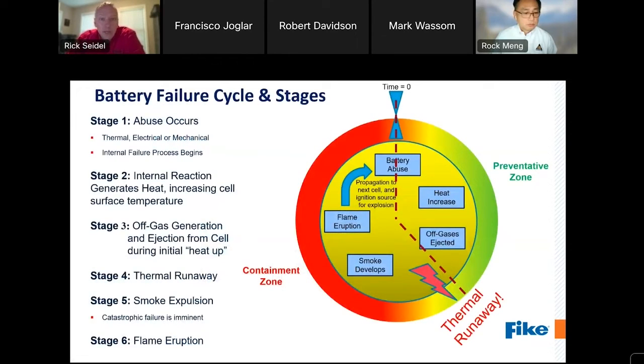There are many ways you can visualize the failure cycle of lithium-ion batteries, and I feel one effective way is by thinking of it as a clock or a round cycle, as failure to interrupt the cycle or stop the clock will result in a continuously growing hazard in both intensity and damage. Any form of abuse to any given cell will start the clock ticking from midnight, with thermal runaway occurring at about 5 o'clock. It's important to recognize that we do have the opportunity to detect failures and pending hazards before thermal runaway, which I will refer to as the preventative zone, whereas once thermal runaway begins, we are squarely in a containment zone and have different options to consider.